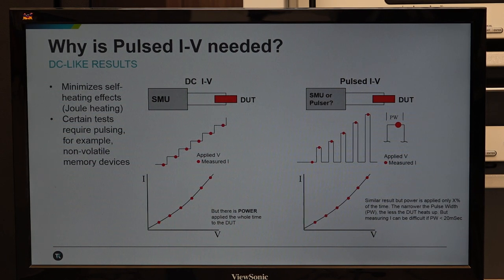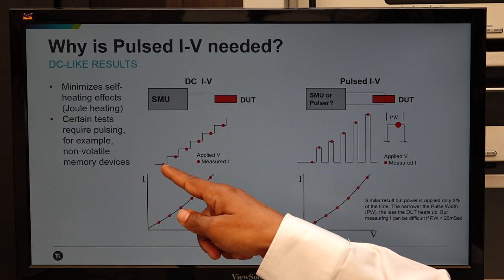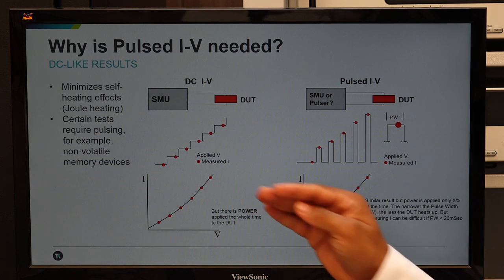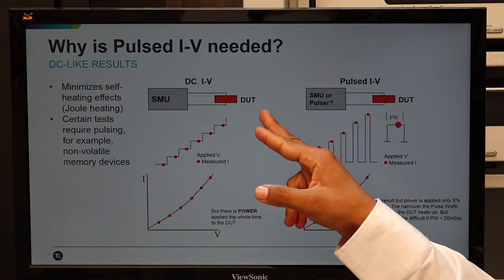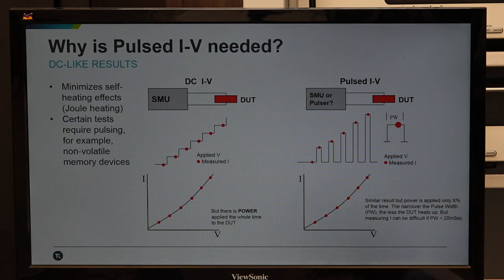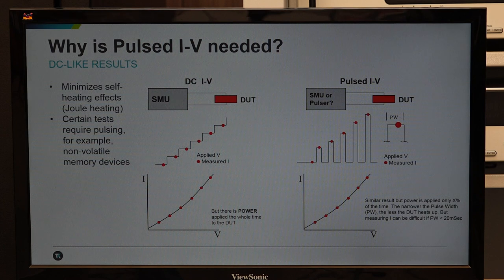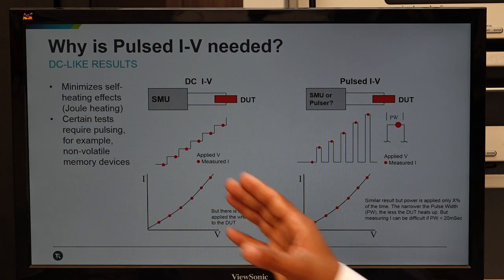The third important aspect of parametric analyzer is pulse IV measurement. In standard IV measurement, voltage is applied throughout the experiment in a step-wise manner, resulting in continuous current flow. When working with very small devices — nano film, thin film, thick film — if voltage and current are applied for longer time, it can create problems like Joule heating and self-heating of the material. Since temperature causes changes in resistance, IV characterization can change. To avoid Joule heating, researchers adopted pulse IV measurement.